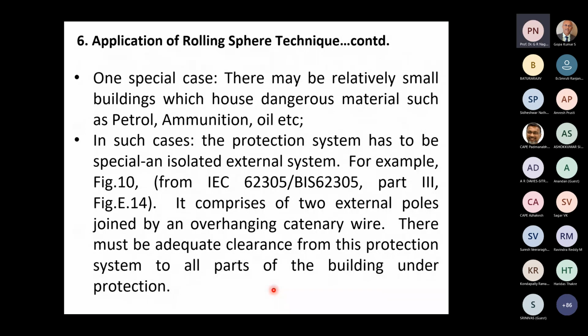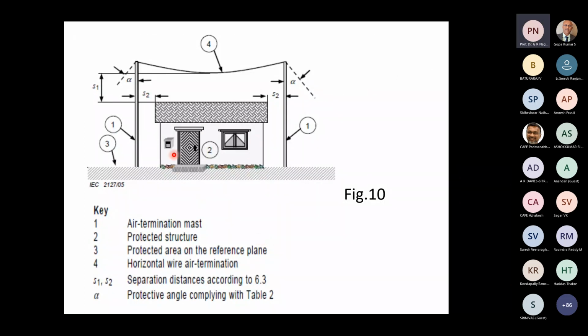Now, one very special case is that there may be relatively small buildings which house dangerous, that means ignitable, material such as petrol, fuel, ammunition, oil, etc. In such cases, the protection system has to be what we call an isolated external system. For example, figure 10 shows the building where ammunition or petrol is stored. Therefore, a strike to the building is not at all desirable.